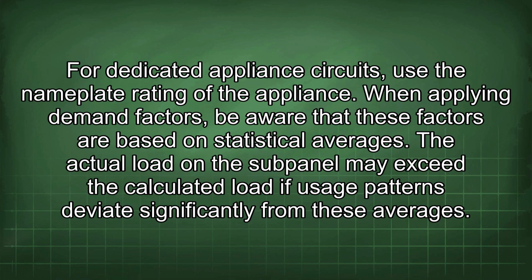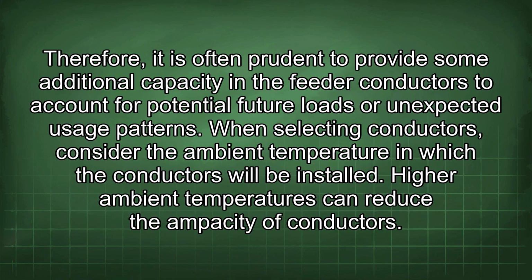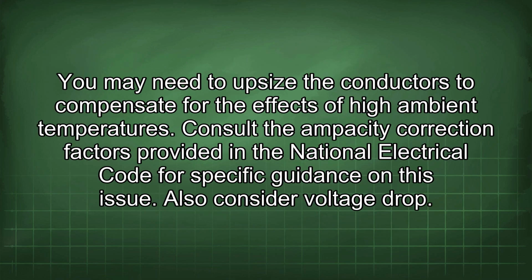When applying demand factors, be aware that these factors are based on statistical averages. The actual load in the subpanel may exceed the calculated load if usage patterns deviate significantly from these averages. Therefore, it is often prudent to provide some additional capacity in the feeder conductors to account for potential future loads or unexpected usage patterns. When selecting conductors, consider the ambient temperature in which the conductors will be installed. Higher ambient temperatures can reduce the ampacity of conductors. You may need to upsize the conductors to compensate for the effects of high ambient temperatures.